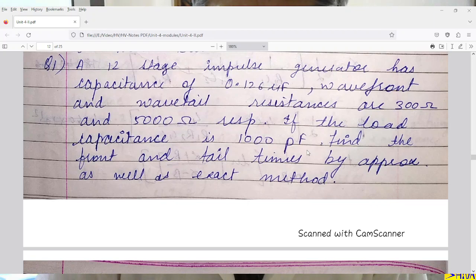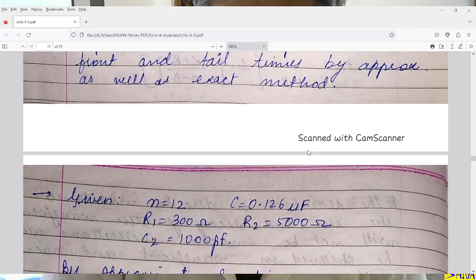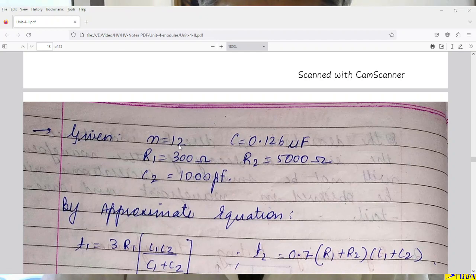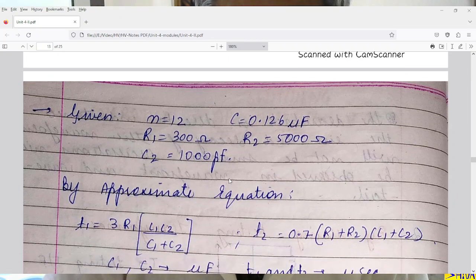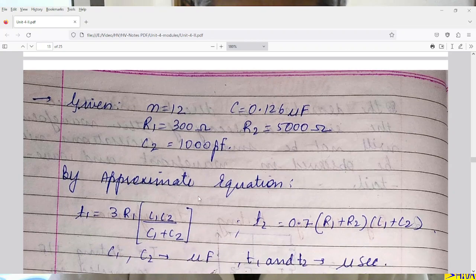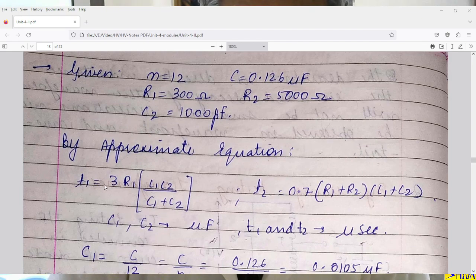I had given you the calculations for time T1 and T2 by approximate method as well as exact method. So in this numerical we have to compute the tail time and front time by both methods. Given: N = 12, C = 0.126 microfarad each, R1 = 300 ohms, R2 = 5000 ohms, C2 = 1000 picofarad. For time T1, the equation is 3 × R1 × (C1 × C2)/(C1 + C2), and T2 is 0.7 × (R1 + R2) × (C1 + C2).